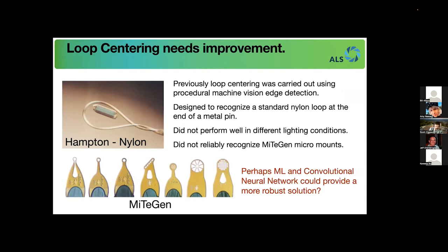This loop centering was carried out using a procedural machine vision technique and was designed to recognize standard tennis-racket-shaped Hampton nylon loops. But it was a little bit finicky. It did not perform very well when lighting conditions were off — if the edge finding didn't work well, it would be hard to see the sample. Then along came MiTeGen, which started making all these lithographically manufactured mounts in different shapes and sizes, which the researchers loved — but this procedural machine vision technique just did not work with them. So we started thinking there's got to be a way to use machine learning and convolutional neural networks to do more intelligent recognition of these sample mounts to make our pipeline more robust.